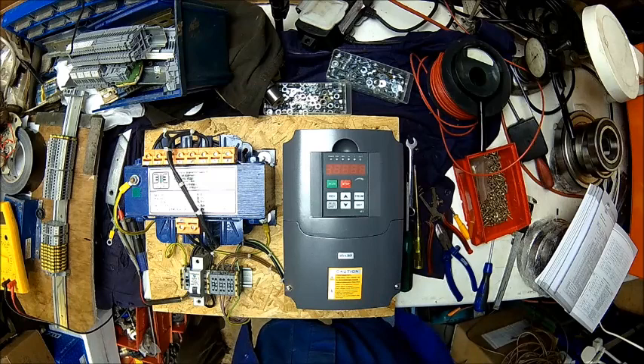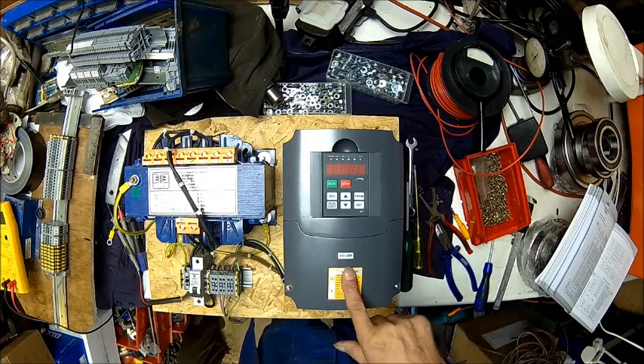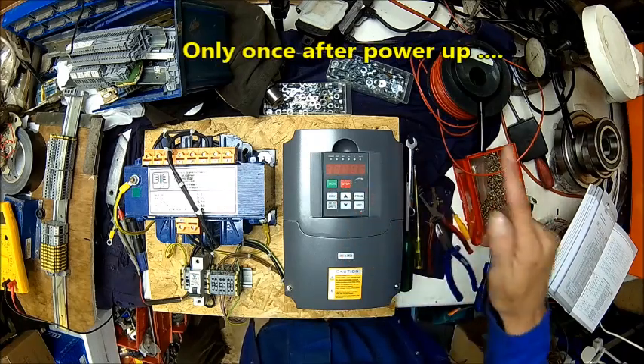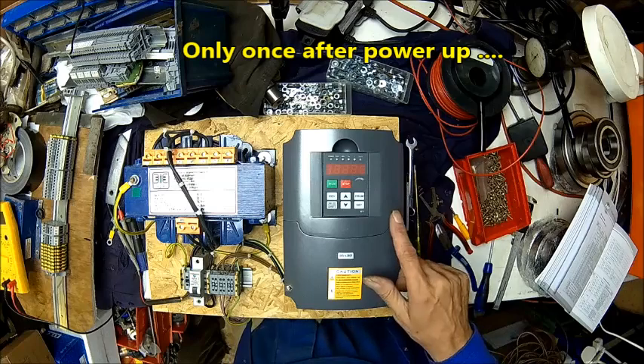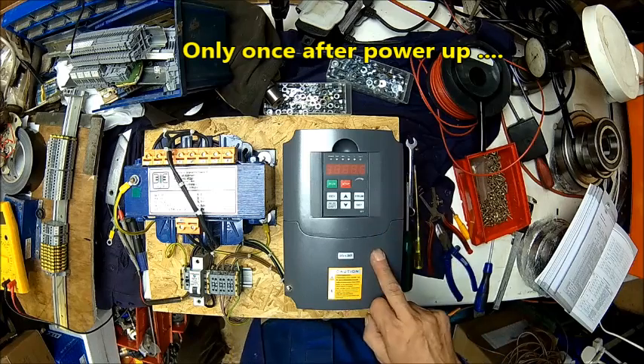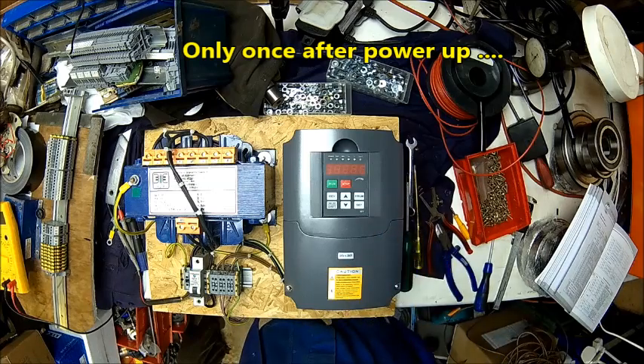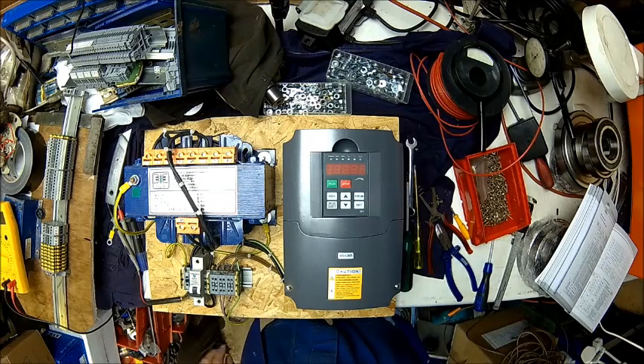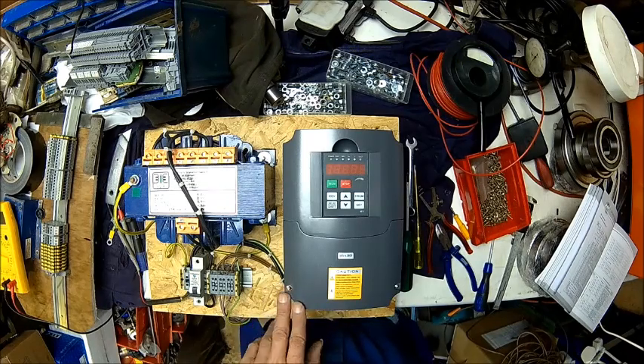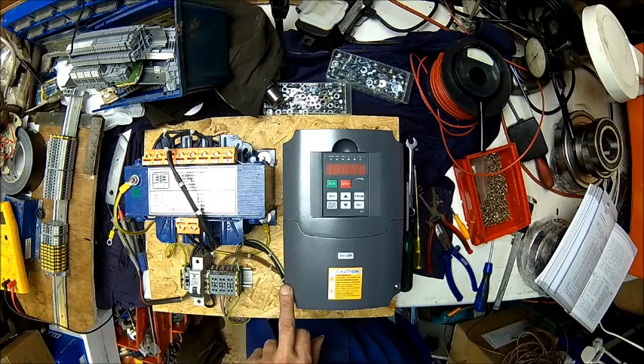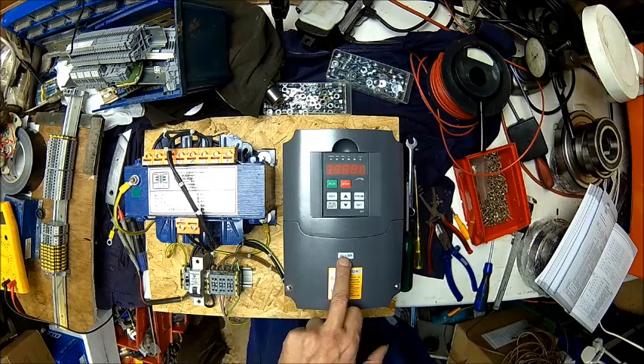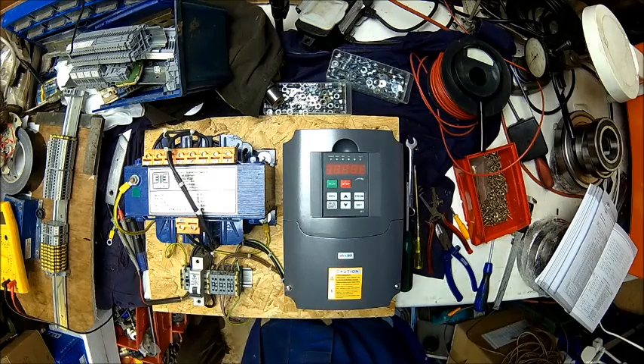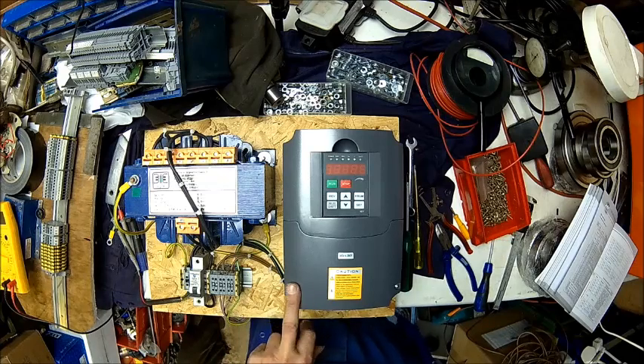You can easily change that with the appropriate parameter. Just set the max voltage to whatever you want and leave the frequency as it was, 50 Hz. And also the run command. At the moment you need to press the run button. If you don't want that, it needs the link and changing one parameter, and that's about it. It's a standard Huanyang inverter, 4 kilowatt, 400 volts. Oh, it says 380 here, plus minus 20%. So we read at the top edge of the inverter rating with 440 volts.